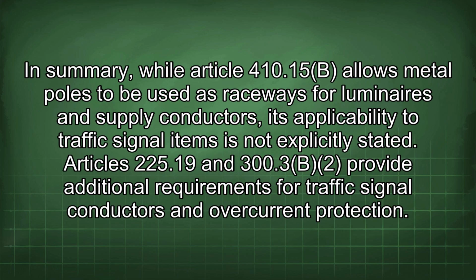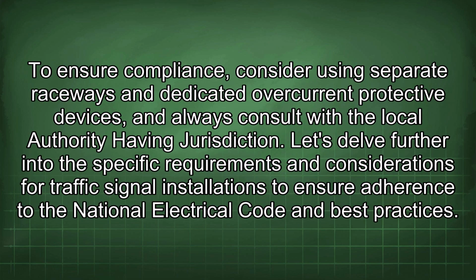In summary, while Article 410.15(B) allows metal poles to be used as raceways for luminaires and supply conductors, its applicability to traffic signal items is not explicitly stated. Articles 225.19 and 300.3(B)(2) provide additional requirements for traffic signal conductors and overcurrent protection. To ensure compliance, consider using separate raceways and dedicated overcurrent protective devices, and always consult with the local authority having jurisdiction. Let's delve further into the specific requirements and considerations for traffic signal installations to ensure adherence to the National Electrical Code and best practices.